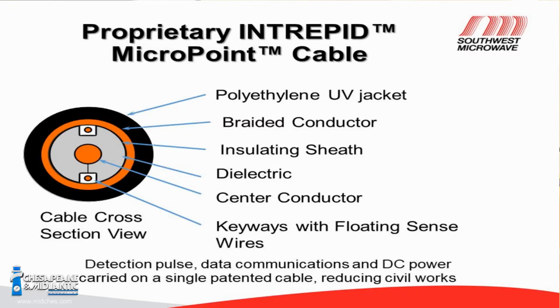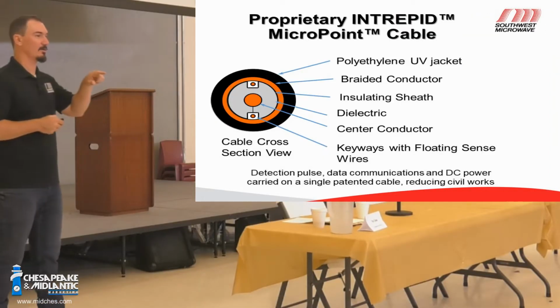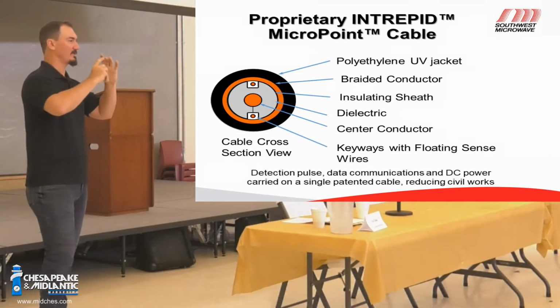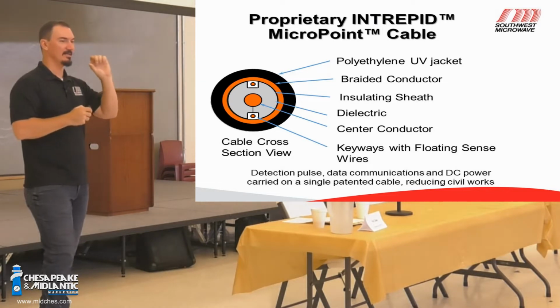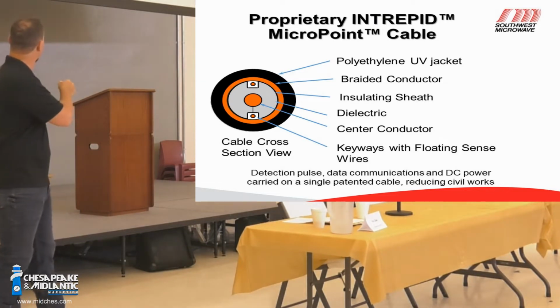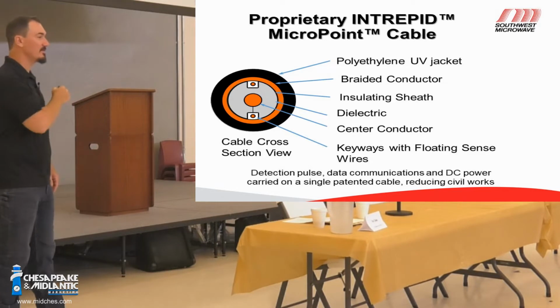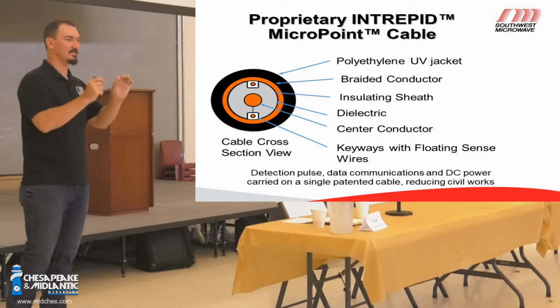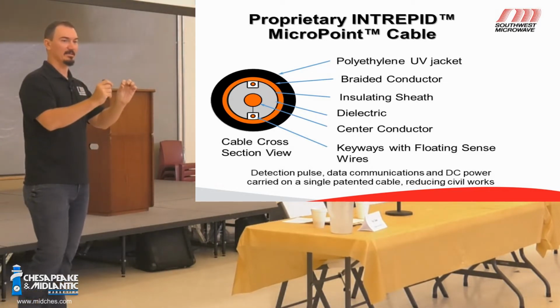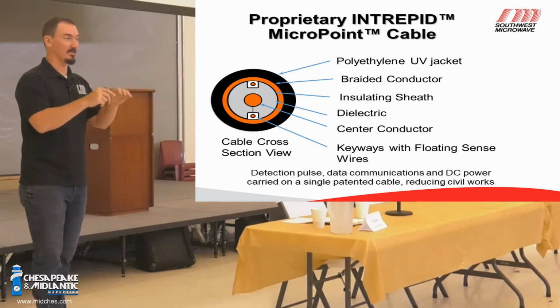All right, so this is the breakdown of the sensor cable. Our sensor cable is a 4-conductor copper-based sensor. The middle conductor, this little guy right here, doesn't move. It's solid. It's a copper core surrounded by a dielectric with 2 small keyways cut into that dielectric. Right? These little guys right here are open. And within those openings, there's 2 very small sensor wires placed in there. Those sensor wires move. They can move around.